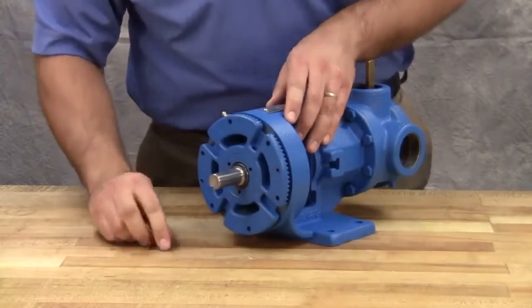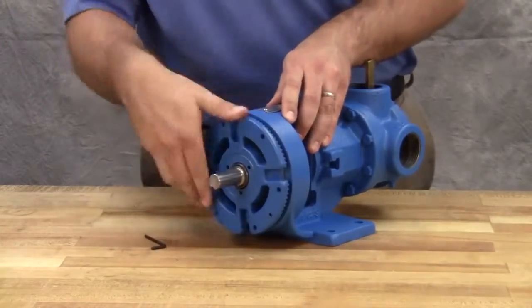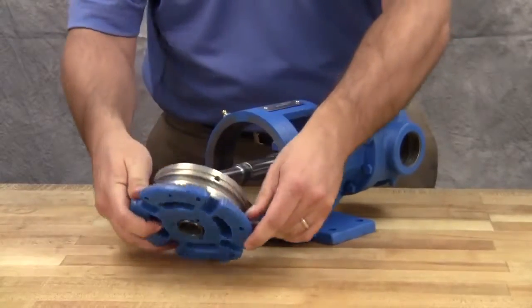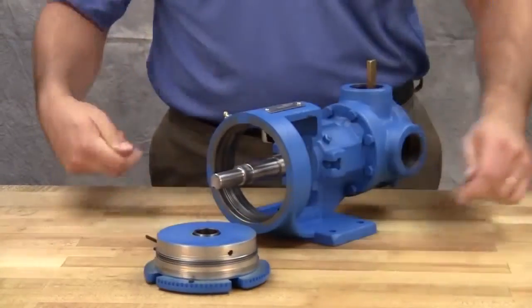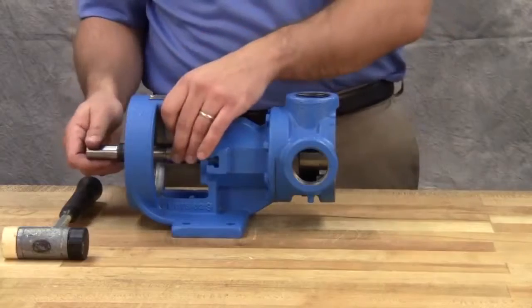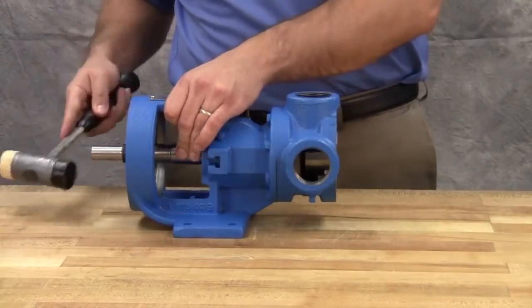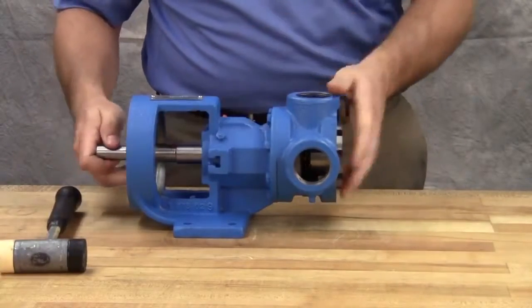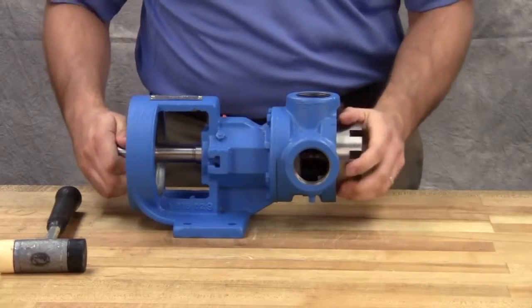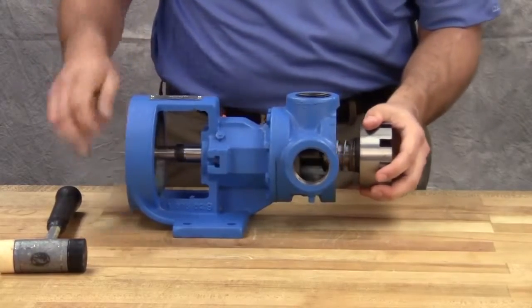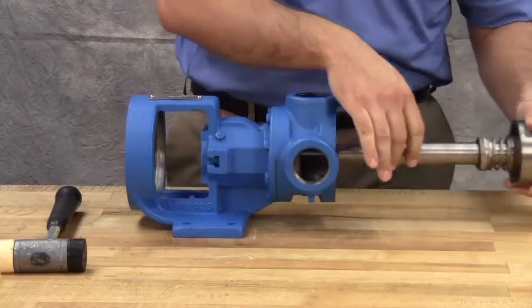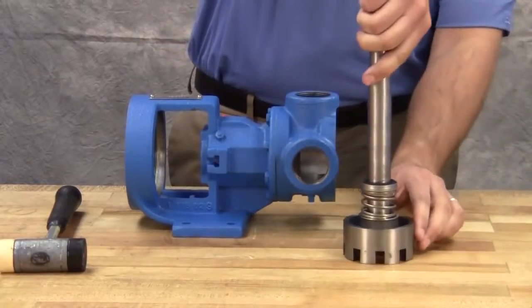On larger pumps, remove a pair of half-round rings from under the inner spacer collar from the shaft. Note that H and HL size pumps do not have these rings. The rotor and shaft assembly can now be removed from the pump. A soft-headed hammer may be needed to tap on the end of the shaft for removal. Take care in removing the rotor and shaft to avoid damaging the bracket bushing.